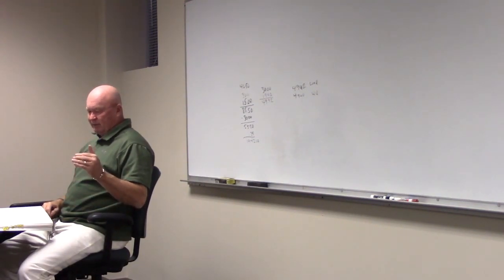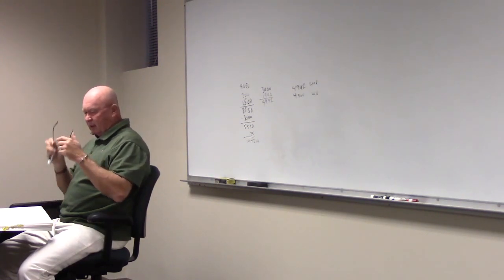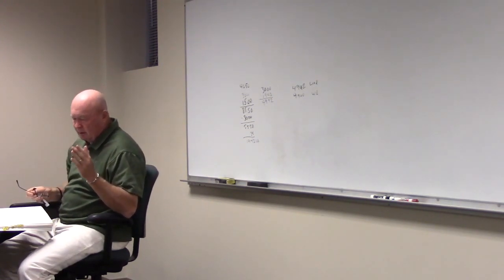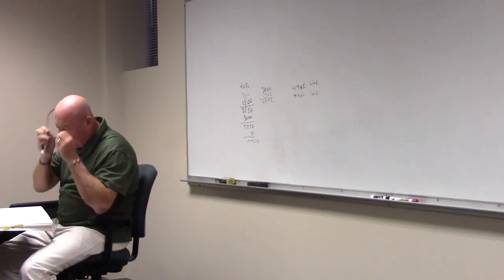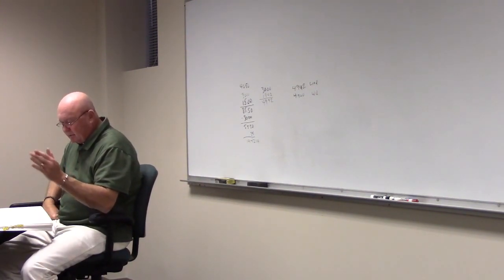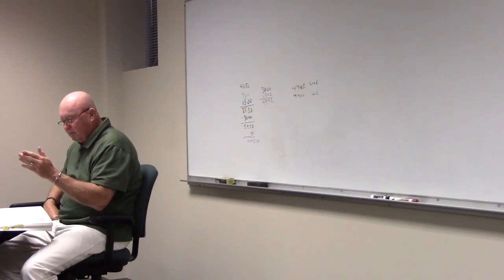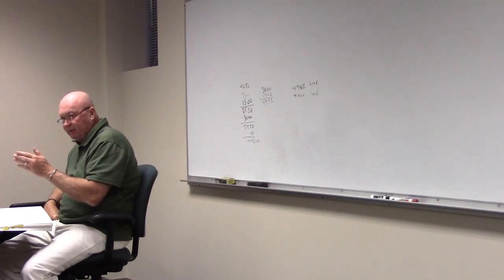So we look there. 220.55 says number of appliances. Now there's 3 different columns. The first column says up to less than 3.5. Column B says 3.5 to 8.75. Column C says not over 12. Is that the column we're in?